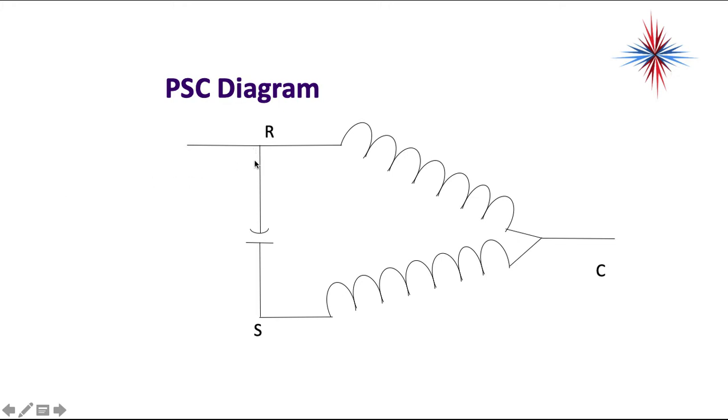Now the difference is we have a run capacitor that is wired in series and if you look at this electronically this is in series with the start winding. There's no switch here so when this motor's running that capacitor and that start winding is constantly getting power.